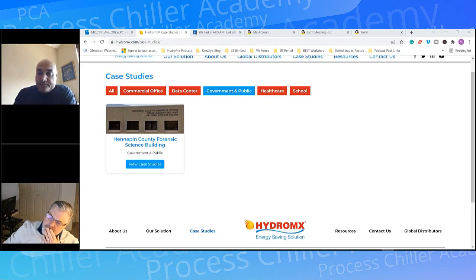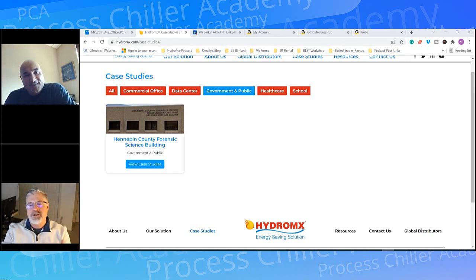So Berkin, let me put my business owner technician hat on. You're telling me that if you've got a large industrial or medium-sized brewery—let's say Budweiser, the big guys—using these monster chillers running a 50-50 mix of propylene glycol, you can put your product in the same concentration, 50-50 mix, and provide the same freeze protection. At 50/50, that gets you down to minus 30 on a PG system—you guys will give about the same freeze protection performance.